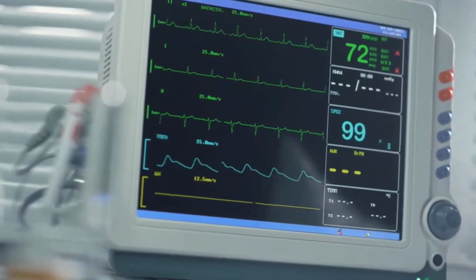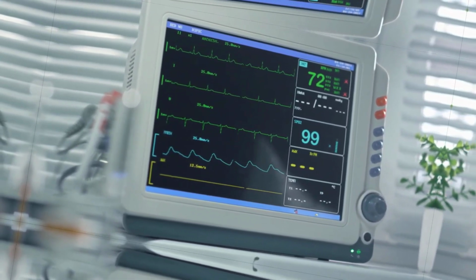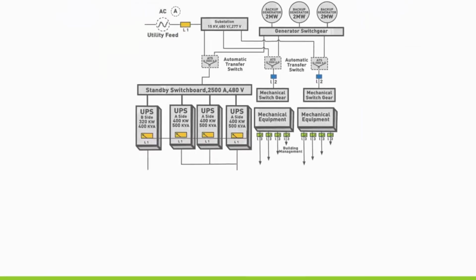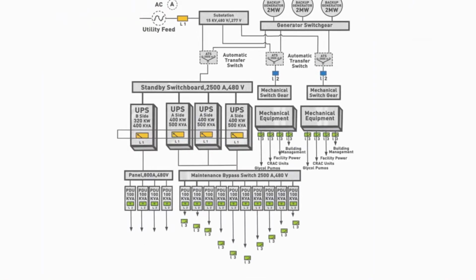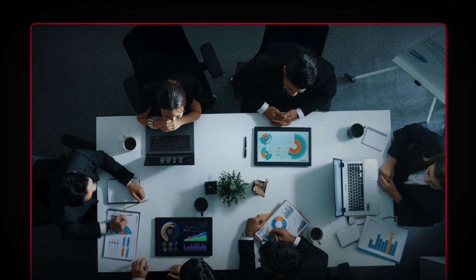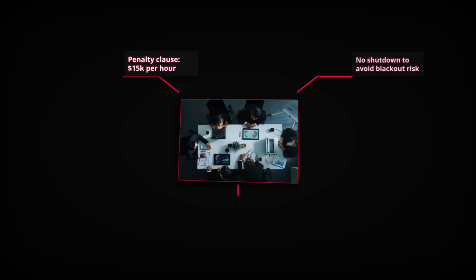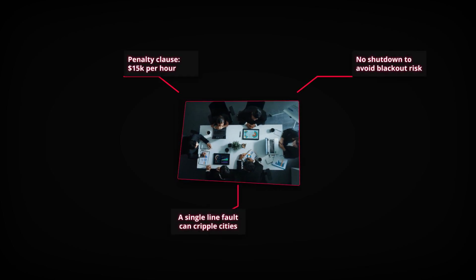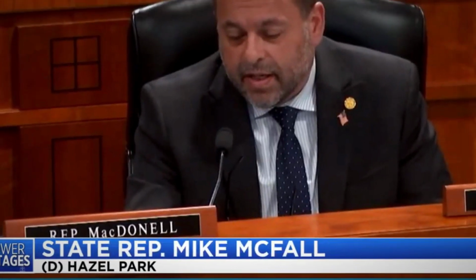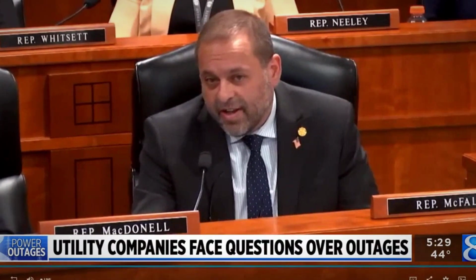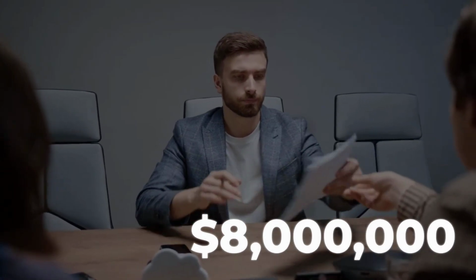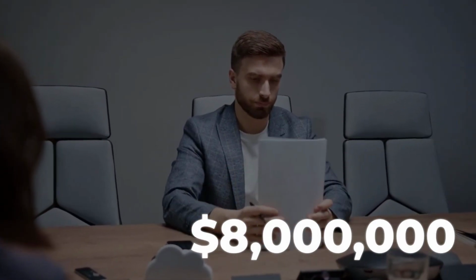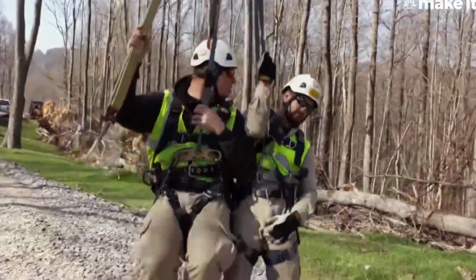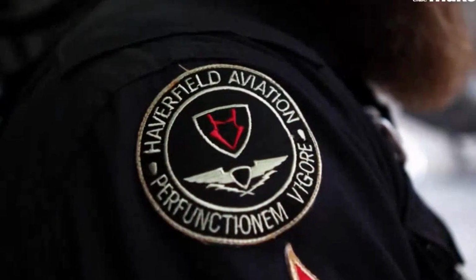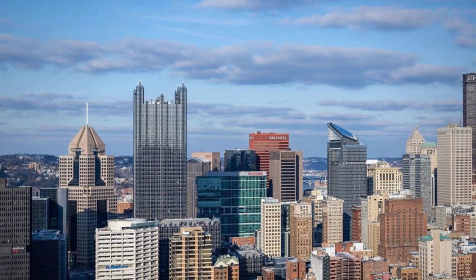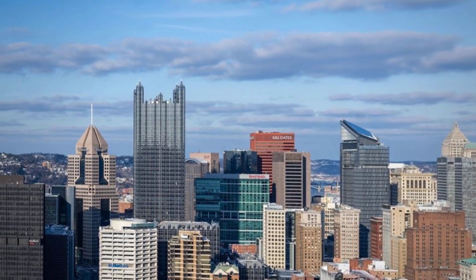Today's grid carries more critical and non-sheddable loads than ever. Hospitals and AI data centers are contractually guaranteed continuous power, often with penalty clauses exceeding $15,000 per hour if service is interrupted. The economic logic is clear. The cost of a planned shutdown, including market penalties and outage compensation, can reach millions of dollars per event. As a result, utilities concentrate risk into live line operations, accepting tightly managed human exposure as the lesser cost compared to systemic instability.